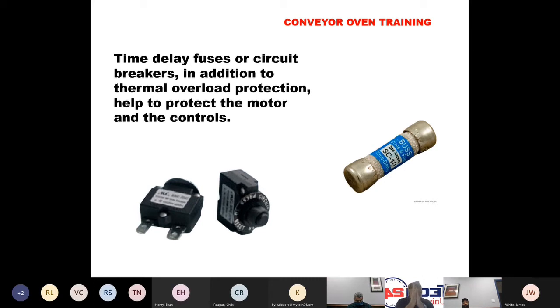If you're not getting voltage to a motor or voltage to a contactor coil, you may have a problem with either mini breakers or fuses or even thermal overload protection that helps protect the motor and controls. So if you don't have voltage at a motor, trace back through your circuit and see what's preventing it.